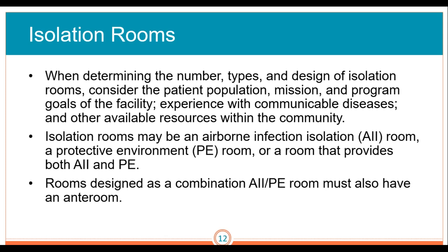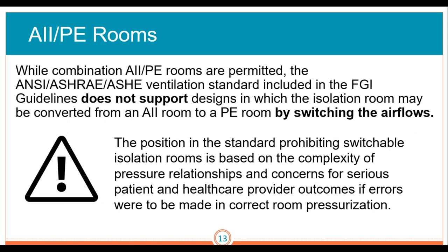Isolation rooms may be an airborne infection isolation room (AII), a protective environment, or a room that provides both AII and a protective environment. Rooms designed as a combination of AII and PE room must also have an ante-room. While combination AII and protective environment rooms are permitted, the ANSI/ASHRAE ventilation standards included in the FGI guidelines do not support designs in which the isolation room may be converted from an AII room to a PE room by switching the air flows. This is due to concerns for serious patient and healthcare provider outcomes if errors were made in correct room pressurization.